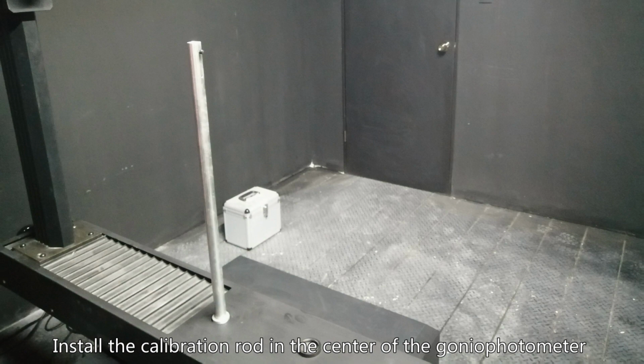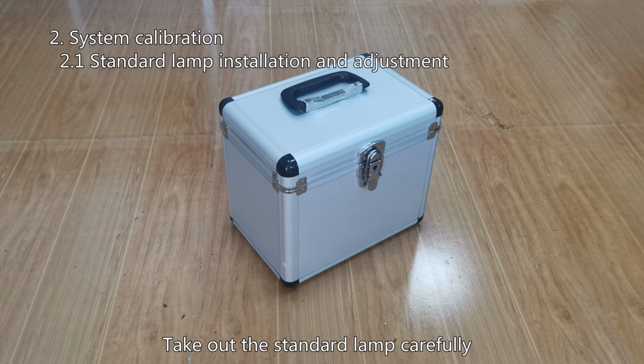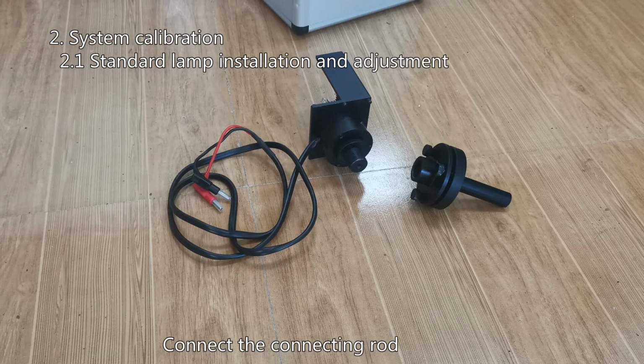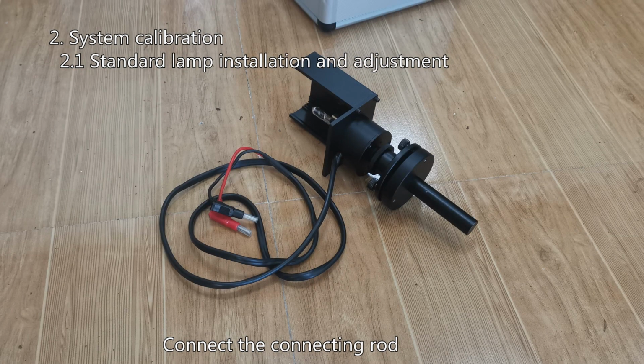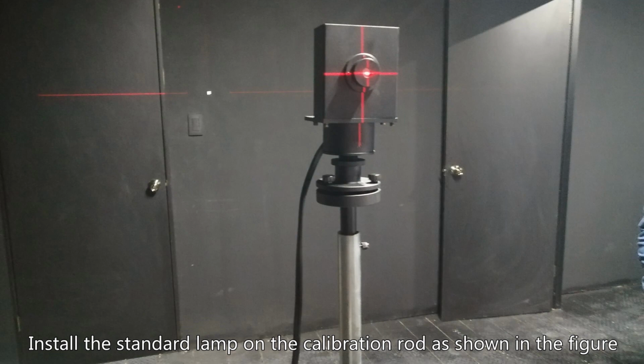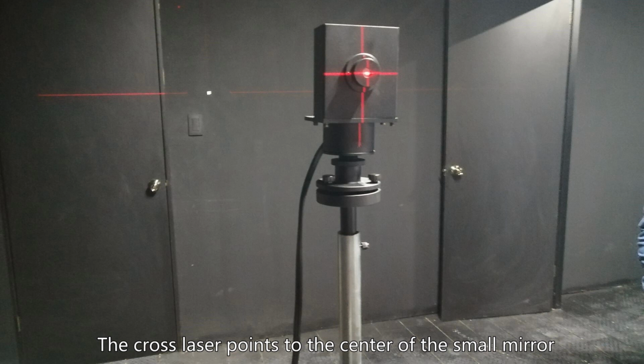Install the calibration rod in the center of the goniophotometer. Take out the standard lamp carefully. Connect the connecting rod. Install the standard lamp on the calibration rod as shown in the figure. The cross laser points to the center of the small mirror.